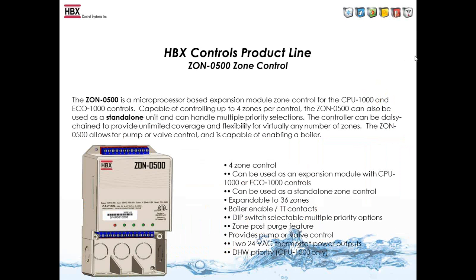The Zone 500 is either a standalone control, so it can work independent of our controls, or you can connect it with our 1000 controls and have a lot more capabilities of the zoning. So this will connect with either an ECO-1000 or the CPU-1000 control. It can control up to 4 zones, either zone pumps or zone valves. So whatever power you put in the control, say 24, 24 comes out. If you put 120 in, 120 comes out.